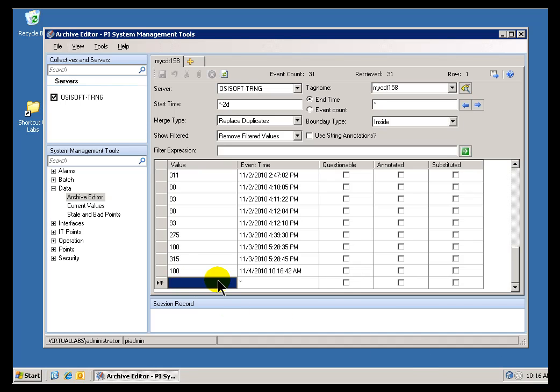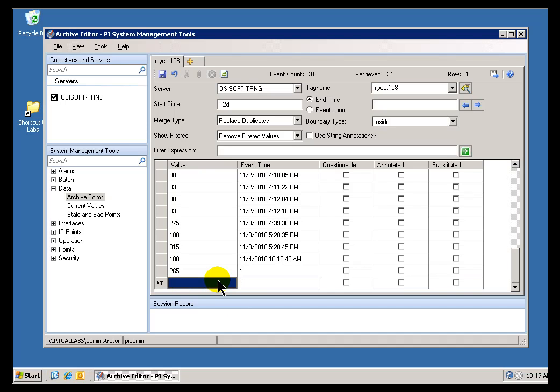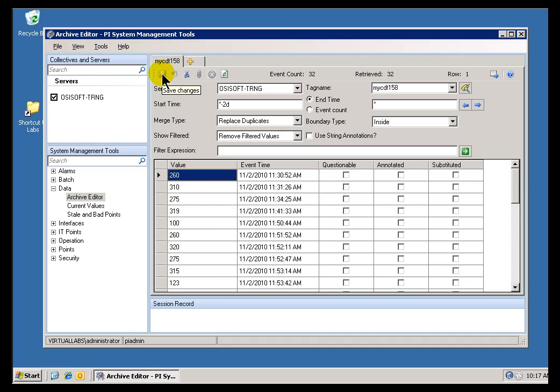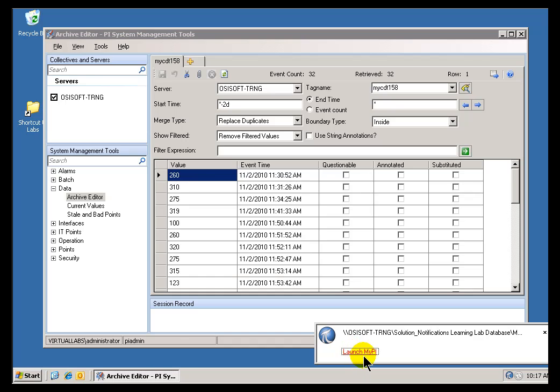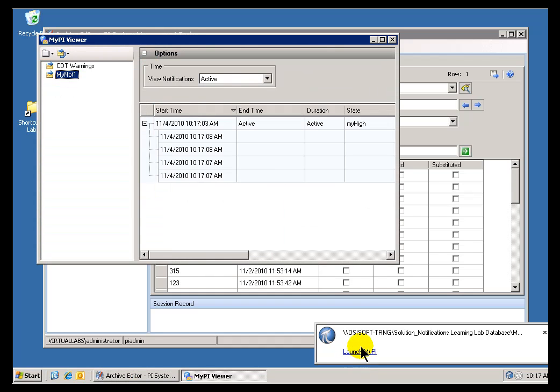And, now, watch what happens if I go ahead and push this to, say, 265. That should be above the 250. We should get a notification here. Yeah. As you can see, we just got the little Desktop Alert saying, hey, take a look at this. We've got something to look at. If I go ahead and launch MyPI, this will give me a tool that I can use to look at this in more detail.